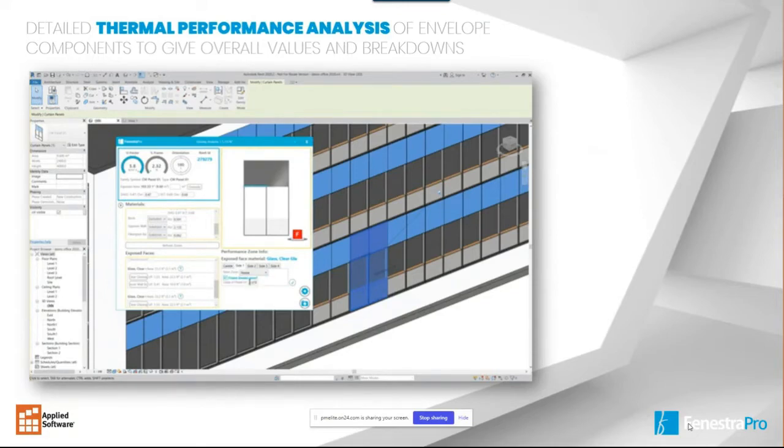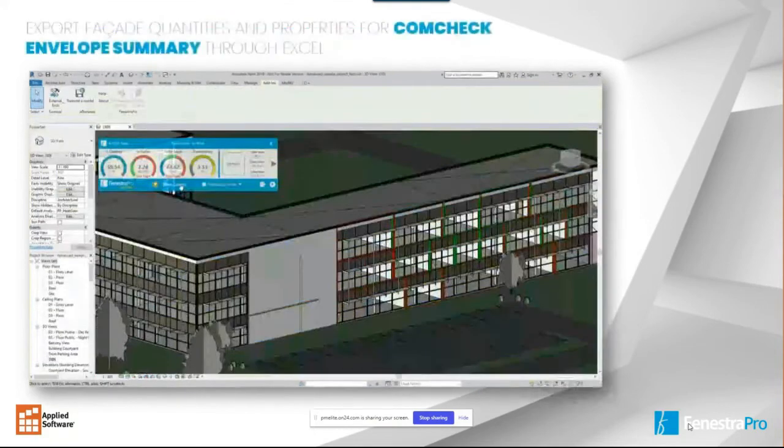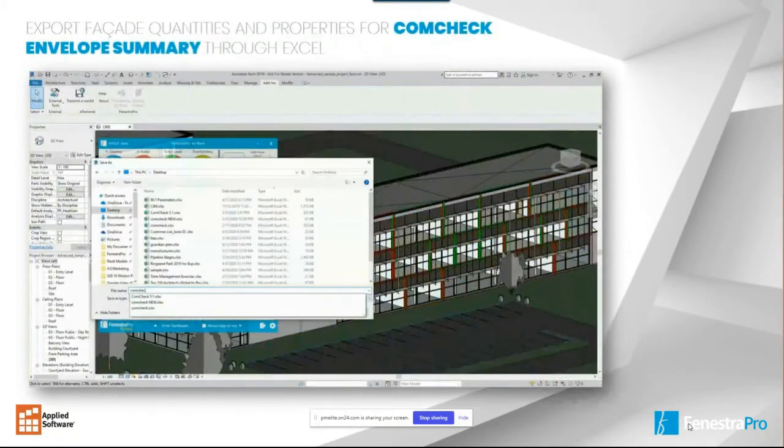Are they solid panels? Are they glass panels? What type of glazing am I using? What type of edge of panel factors am I going to apply, etc. So you can build up a very detailed overall U value, overall thermal performance of that panel, therefore getting an overall thermal performance of your assembly and therefore your facade. So, much more detailed and much more coherent, I suppose.